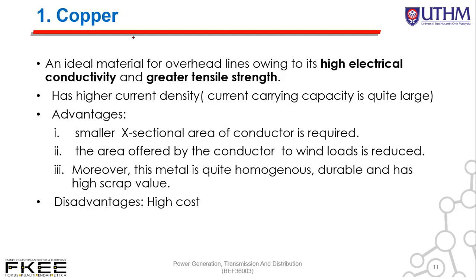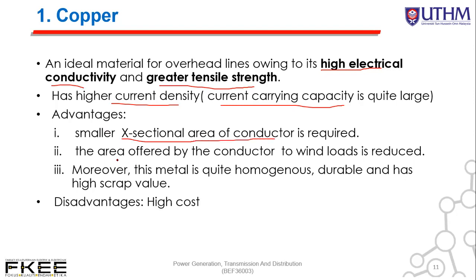First, copper is an ideal material for overhead lines owing to its high electrical conductivity and greater tensile strength. It has higher current density, which means its current carrying capacity is quite large. A smaller cross-sectional area of conductor is required, reducing the area exposed to wind load. This metal is quite homogeneous, durable, and has high scrap value. However, its disadvantage is its high cost.